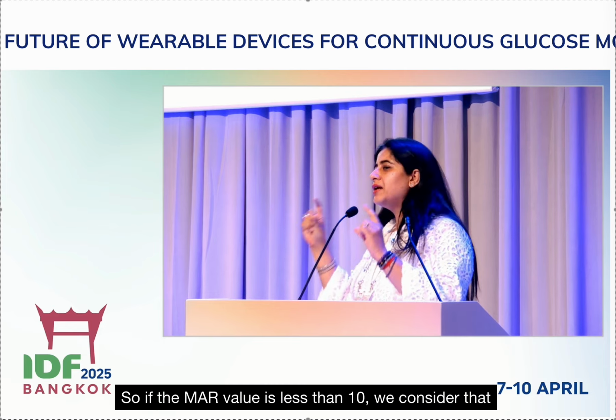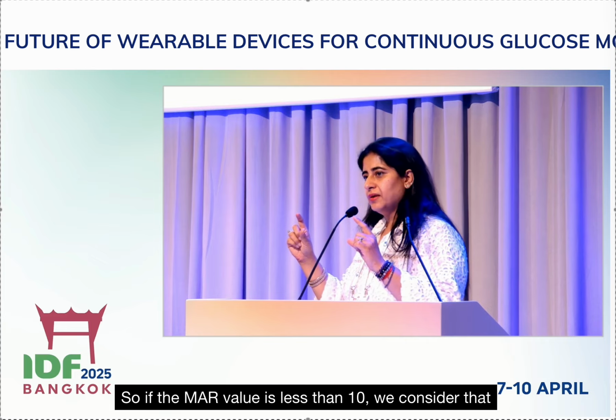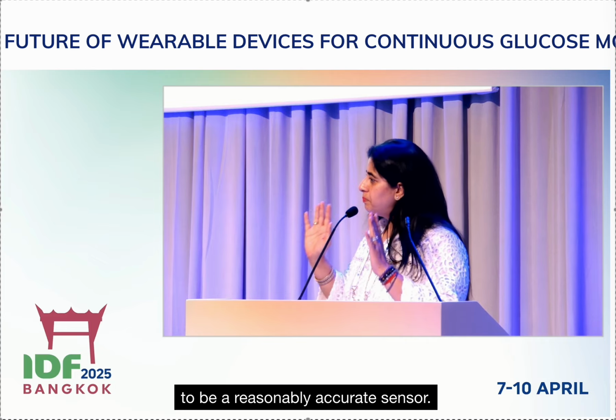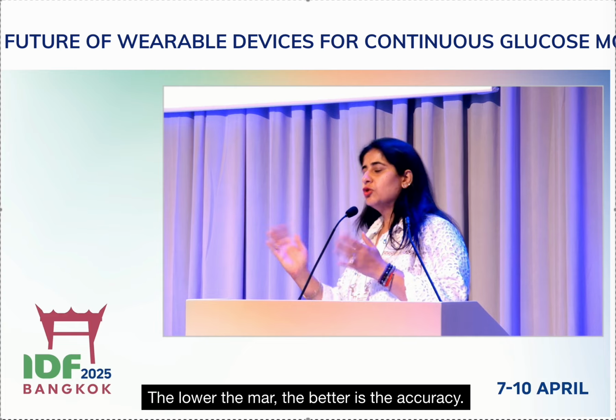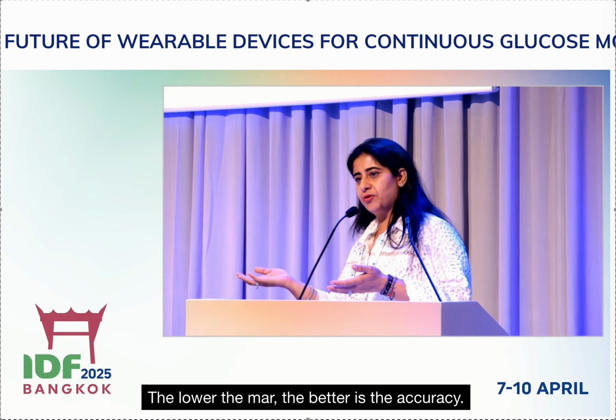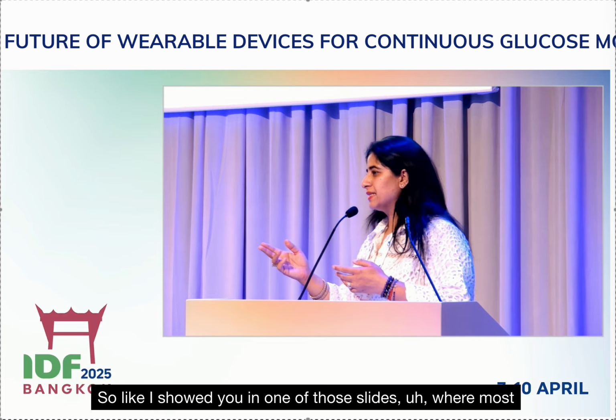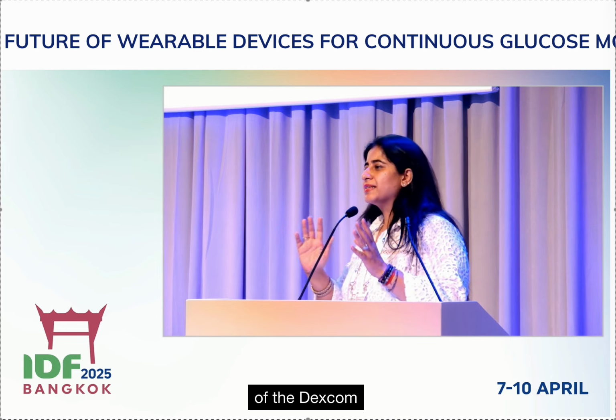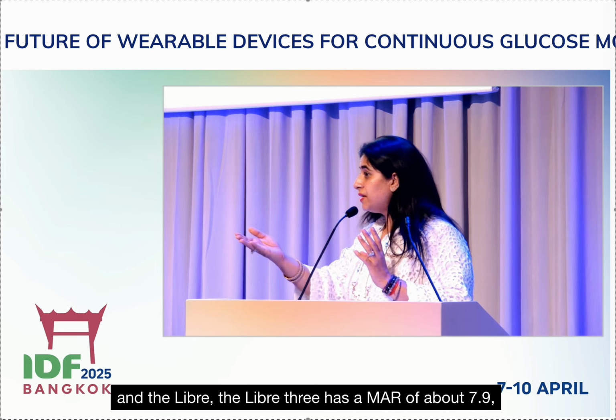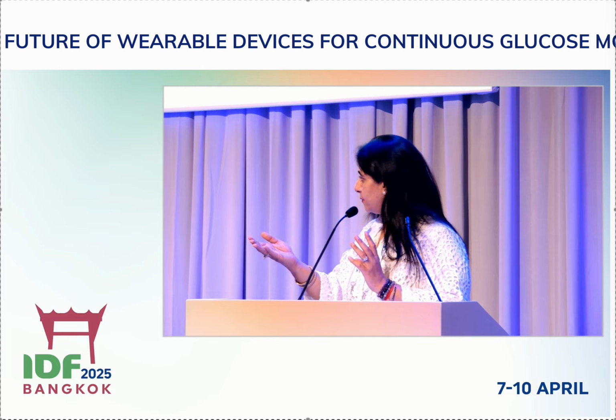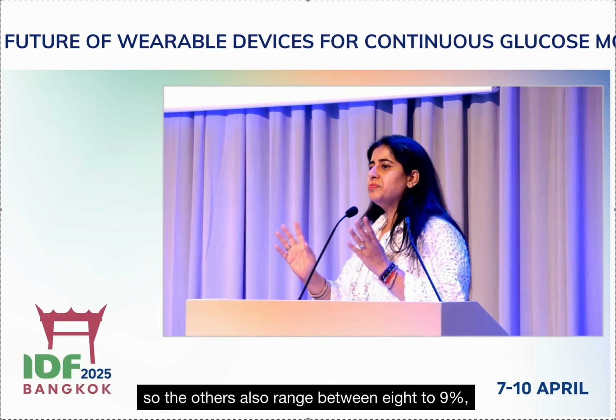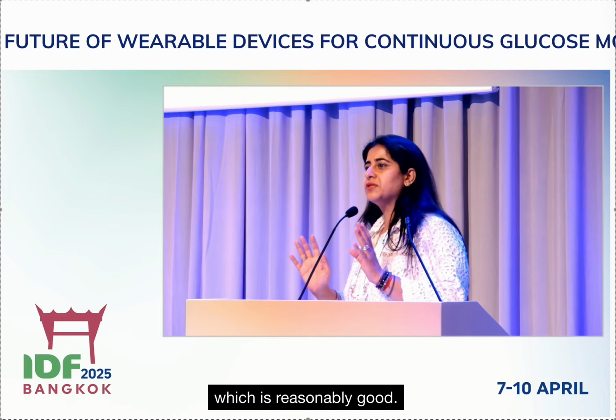So if the MARD value is less than 10, we consider that to be a reasonably accurate sensor. The lower the MARD, the better the accuracy. Like I showed you in one of those slides, most of the Dexcom and the Libre 3 have a MARD of about 7.9. The others also range between 8 to 9%, which is reasonably good.